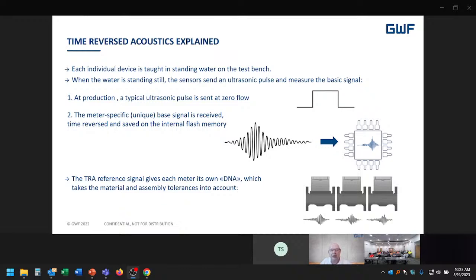They're actually taking an image of what that signal is and putting it in memory. And each meter is slightly different. So by taking this fingerprint, this DNA, it allows the product to start ignoring things such as material and assembly tolerances, and also upstream and downstream conditions, because we're not looking at impacts to when the signal gets there. We're able to look physically at the shape of the signal.